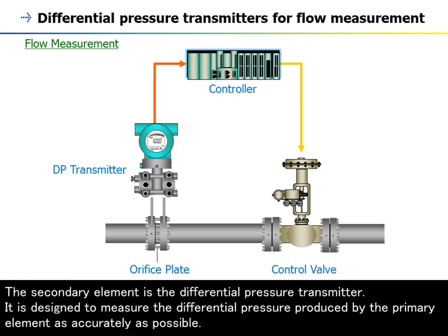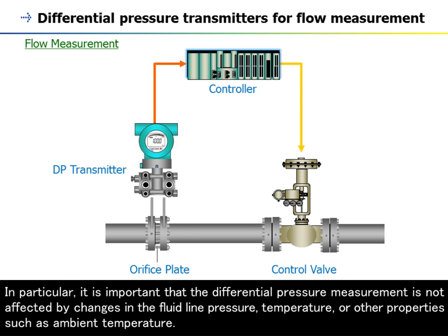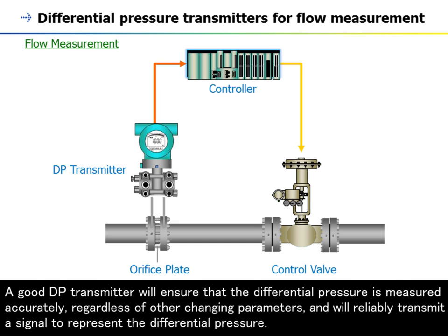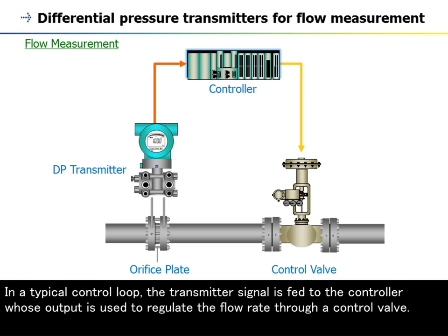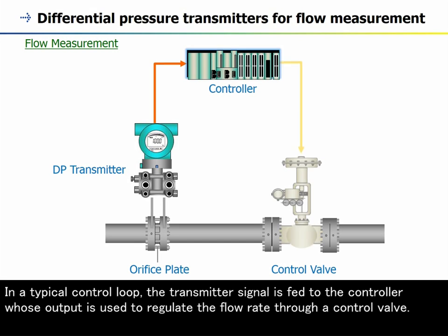The differential pressure transmitter is designed to measure the differential pressure produced by the primary element as accurately as possible. It is important that the measurement is not affected by changes in the fluid line pressure, temperature, or other properties such as ambient temperature. A good DP transmitter ensures accurate measurement regardless of other changing parameters and reliably transmits a signal. The DP flow transmitter output signal may also include square root extraction for flow calculation, although this function is commonly handled in a control system. In a typical control loop, the transmitter signal is fed to the controller, whose output is used to regulate the flow rate through a control valve.